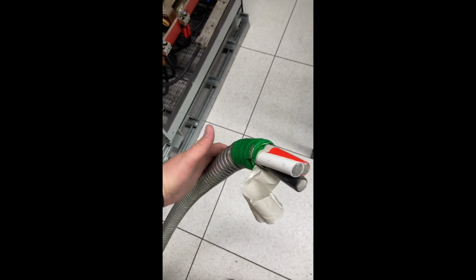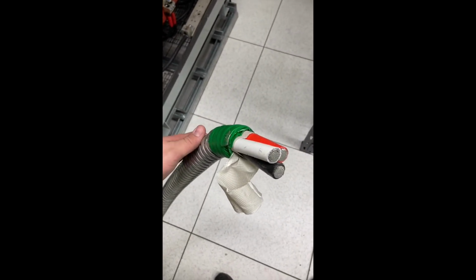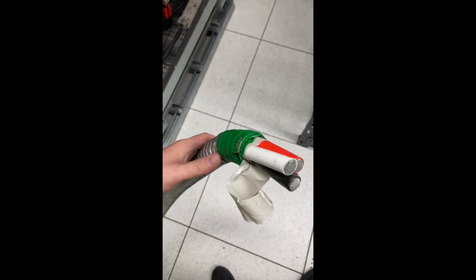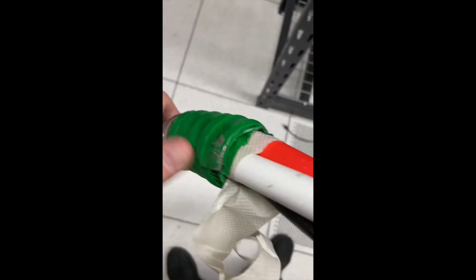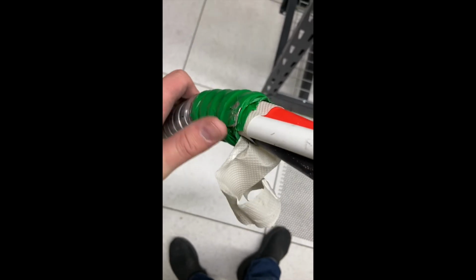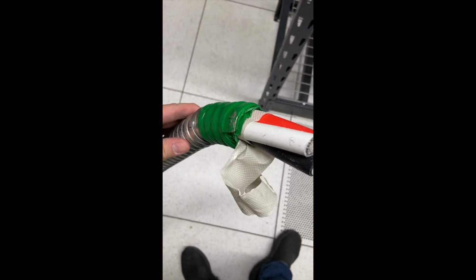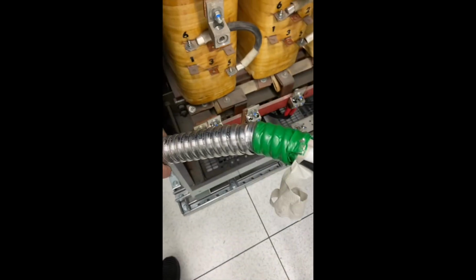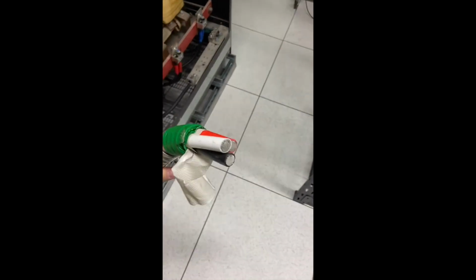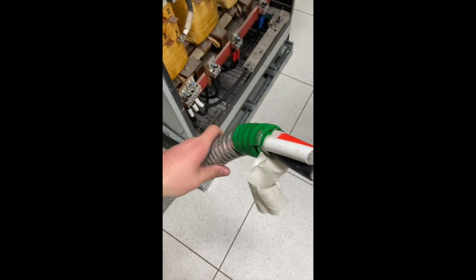That's what goes in the side, and you'll see here in a minute that the sheathing actually comes off, and you can unwind it down to the length you need to get it into the side of the transformer. Then you connect that to H1, H2, and H3 of the primary voltages, and the secondary will run from there.